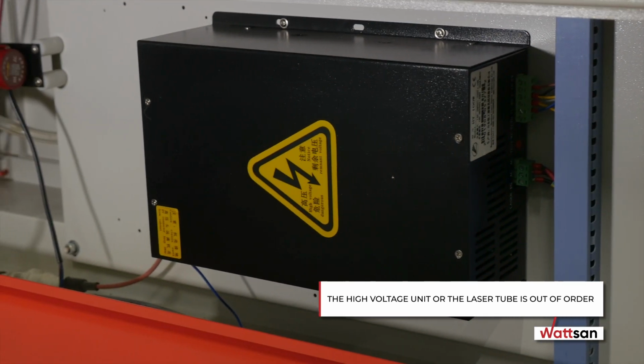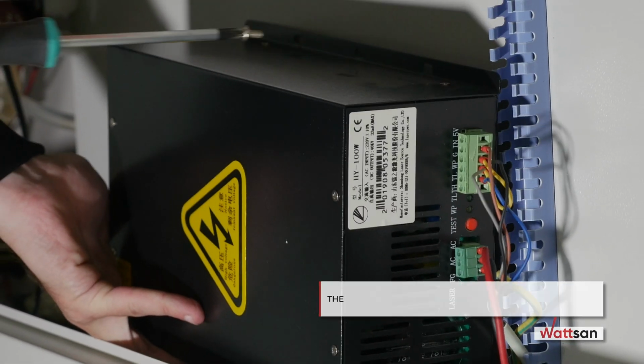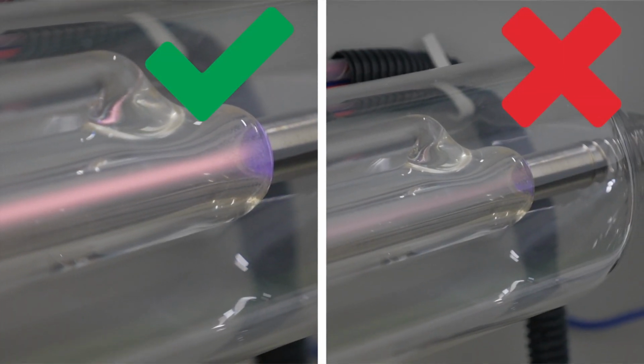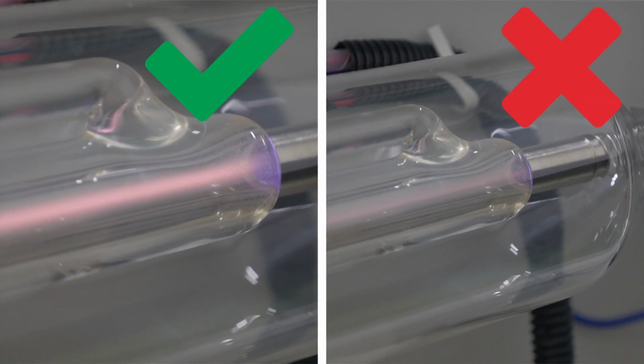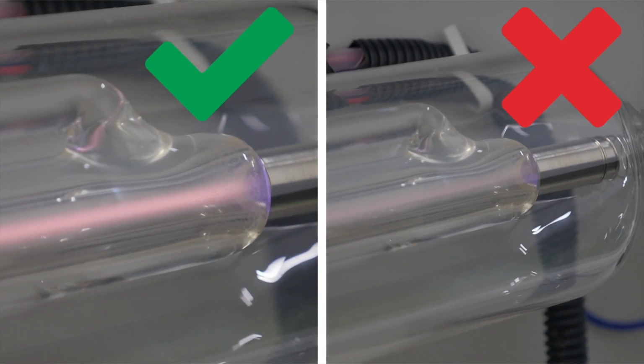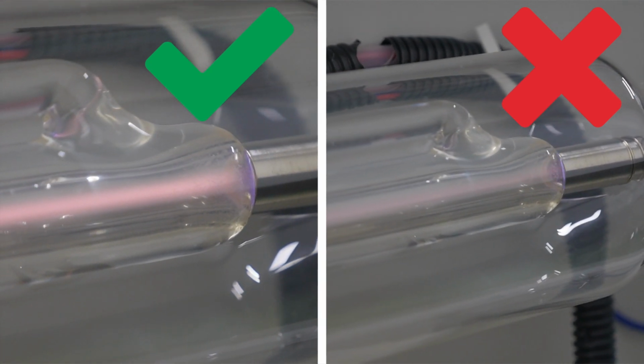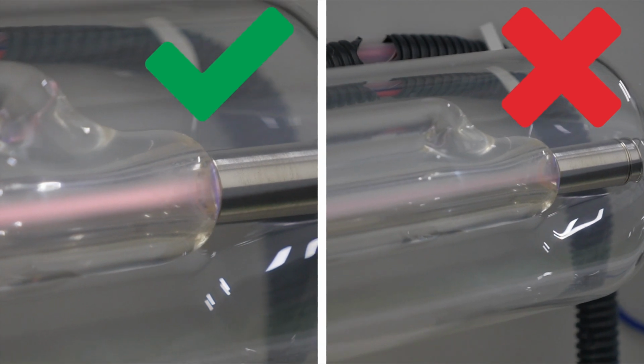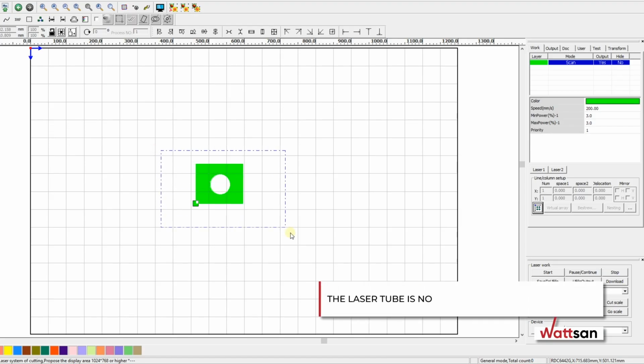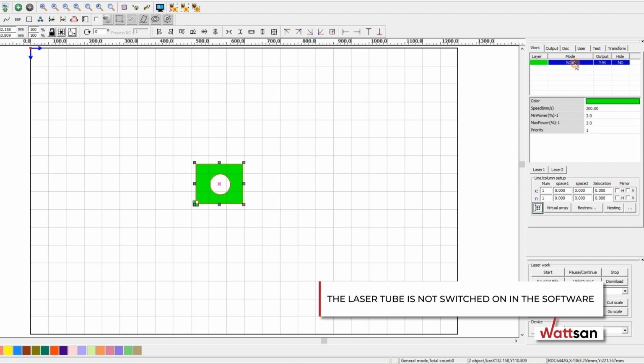9. The high voltage unit or the laser tube is out of order. Still, a faint, barely visible beam in the tube can be observed. With a high voltage unit control plug disconnected, the test button does not light the tube and does not give a pulse. 10. The laser tube is not switched on in the software.